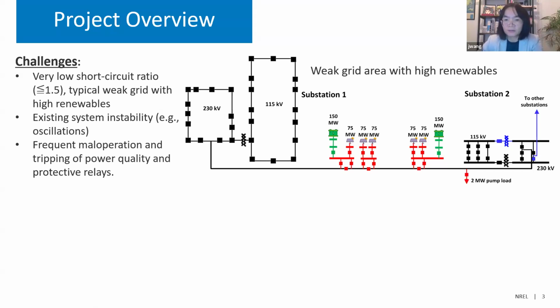For this weak grid area, they have experienced a lot of challenges. First, the SCR can usually go to below 1.5 PU. This is a typical weak grid area for them with a lot of solar plants. And they have already seen some oscillation issues. Additionally, the inverter has fault ride-through problems and doesn't meet the grid requirements. They also have motor starting problems in this transmission line. Additionally, they also see power quality issues and relay misoperation. So those are the key highlighted problems seen in this weak grid area.